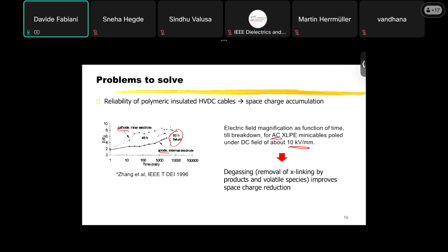So the idea was to use an AC insulation for DC. You have to remove all the cross-linking byproducts and volatile products. In that case, you can reduce space charge accumulation, you can reduce the increase of the electric field, and you can improve the reliability of the cable. So this was the idea that pushed the cable companies, at the end of the 90s, to use polymeric insulation for HVDC. But remember that the electric field was still quite low. The design electric field was below 10 kilovolt per millimeter.